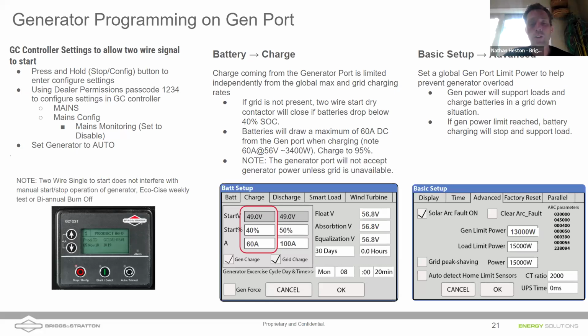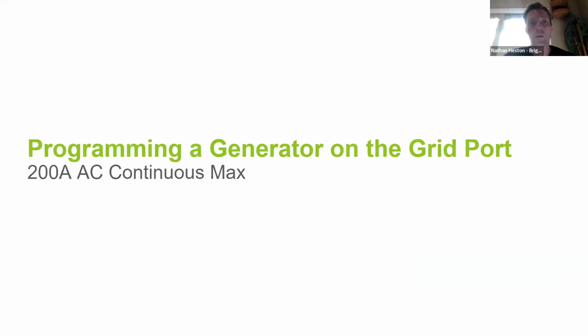Or if we want to prioritize battery charging first, keep in mind you have to have, whatever battery charging value you set up on that generator charge tab in the center of your screen, enough left over to cover the loads of the house. So in some cases with small generators, I would typically recommend prioritizing the load first. And then whatever extra power is left over, the inverter will use that for battery charging. So if you prioritize battery first, you might overload the generator when heavy loads start up and you could get an error message. So keep that in mind.